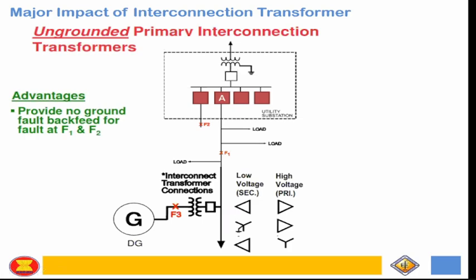And then the advantage of having this ungrounded system: so when there's a fault at F1, since we all know that there's no zero sequence current, wala siyang backfeed for zero sequence current. So yun yung advantage niya. Okay? And then also, if there's a fault at F2, line to ground fault, so wala kang circulation. Wala kang contribution from the DG going to this fault F2, in which hindi mo na ngayon i-consider for coordination. If grounded ito, you need to consider the fault contribution from the DG and then from the grid. Magkaiba yung fault current contribution from the grid and from the DG, then magiging complex yung protection coordination mo ngayon. Okay? So that's the case for the grounded system.